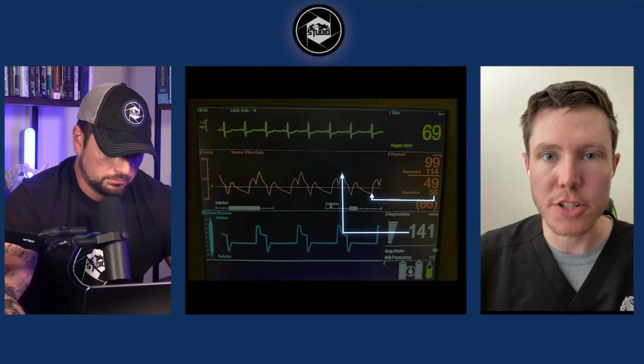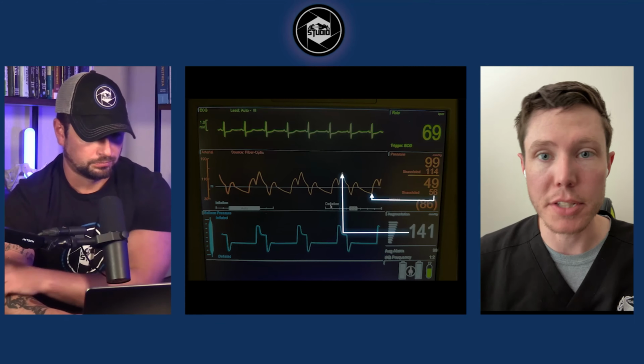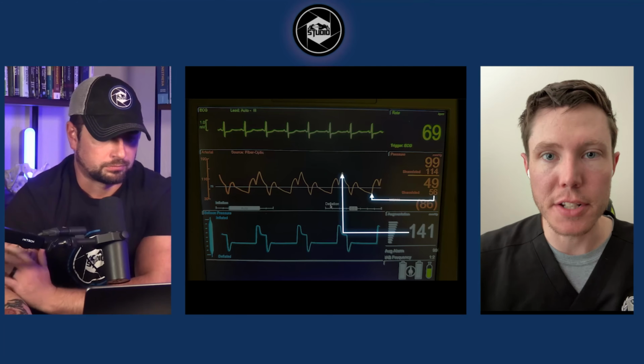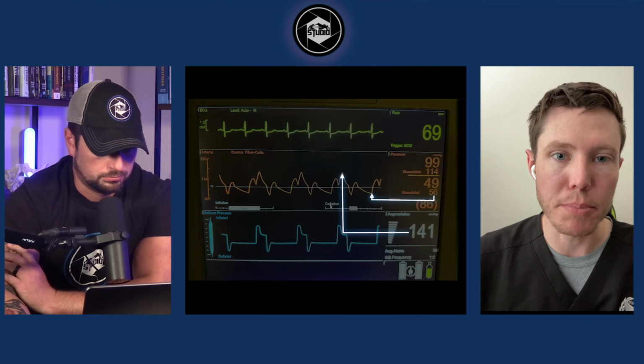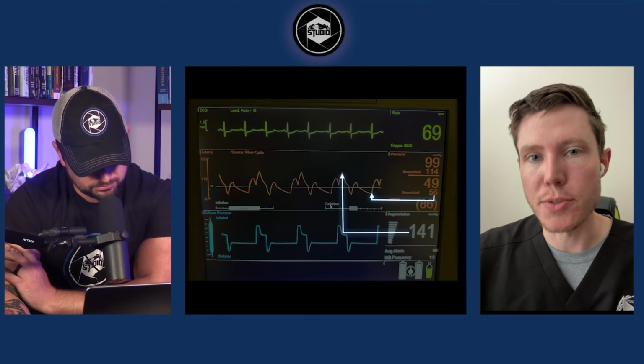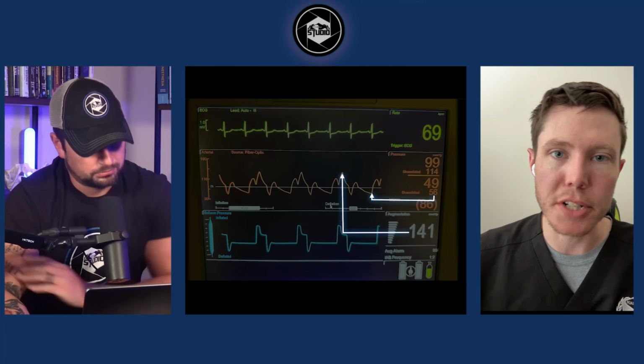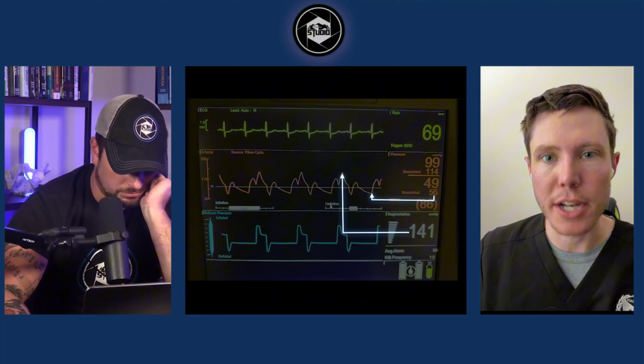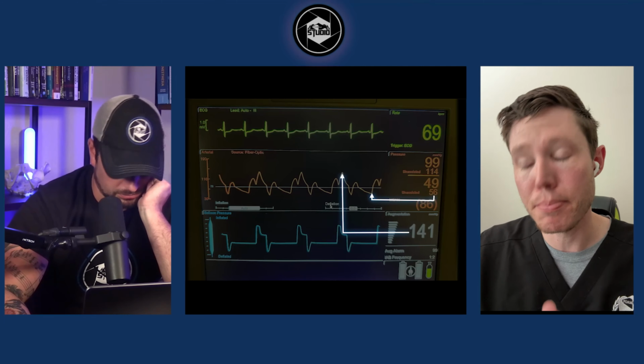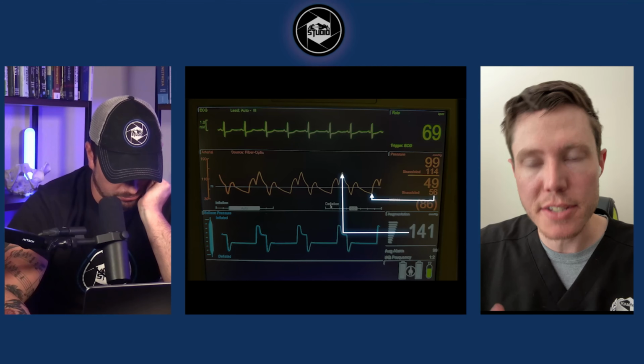Obviously, there are some numbers that you're only going to get off of your balloon pump, like the diastolic augmentation pressure, and your assisted and unassisted pressures, the differences between those two. You can only get those off of the balloon pump. Now, if you didn't have a radial arterial line, the balloon pump numbers, I've charted them. I think they're reasonably accurate, and there's no issue with those, if that's your only access line. And it's important to remember that usually your radial and your balloon pump waveforms are going to be pretty similar, a little bit lower on the radial side, because as distance from the point of pressure increases, you get more resistance just from the walls of the vessels.